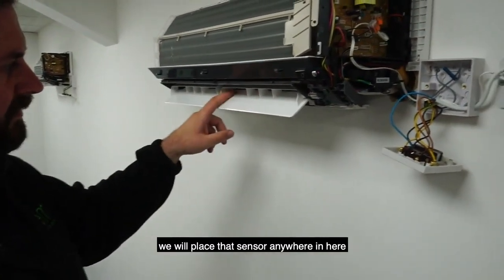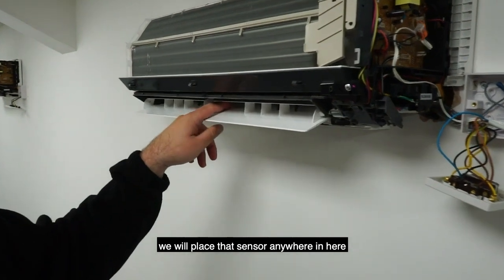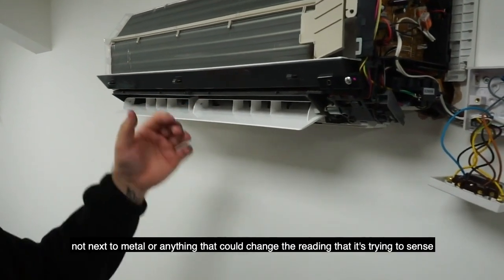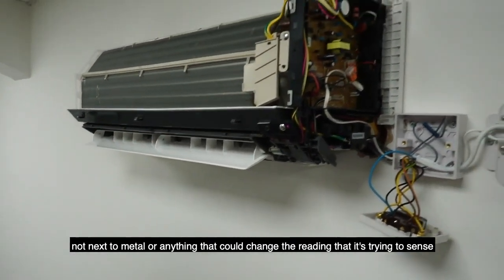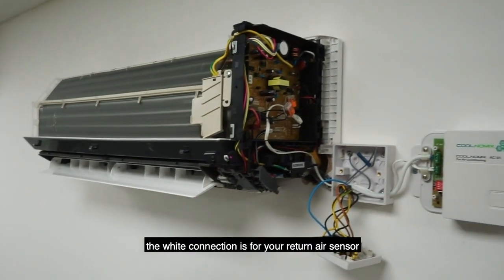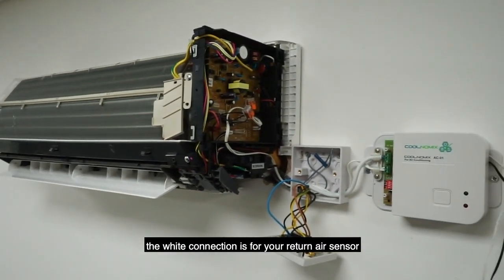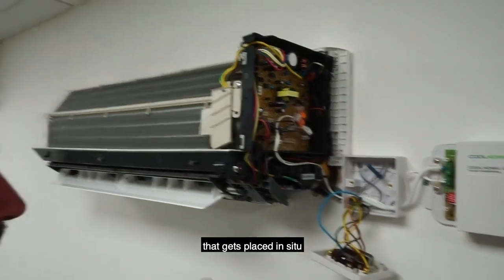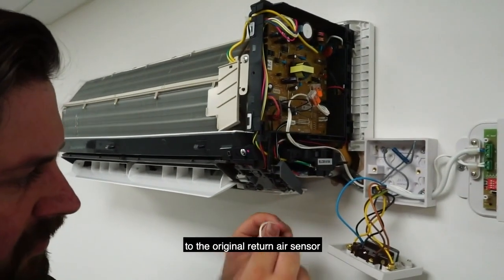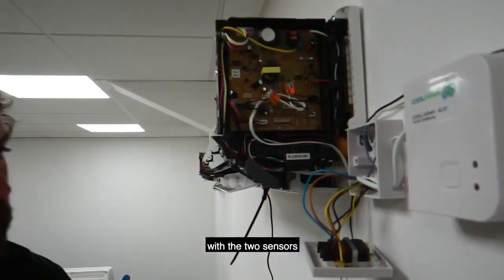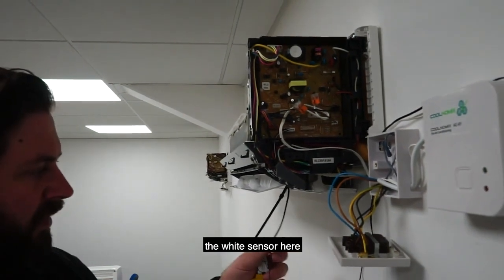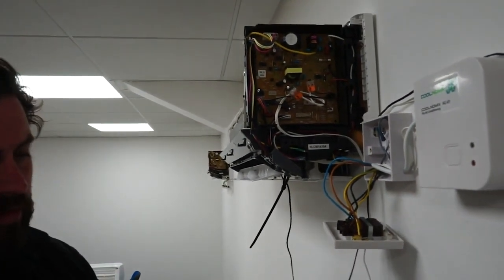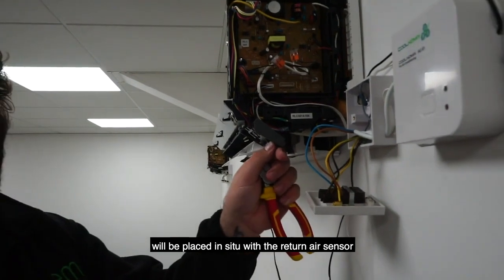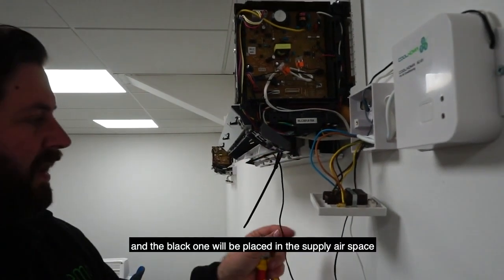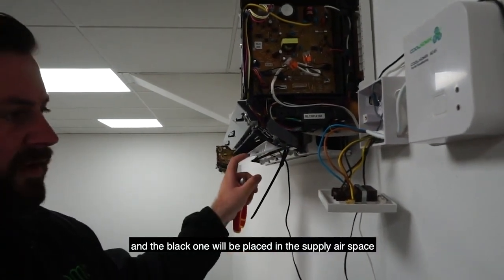We will place that sensor anywhere in here, not next to metal or anything that can change the reading that it's trying to sense. The white connection is for your return air sensor. That gets placed in situ to the original return air sensor. With the two sensors, the white sensor here will be placed in situ with the return air sensor, and the black one will be placed in the supply air space.